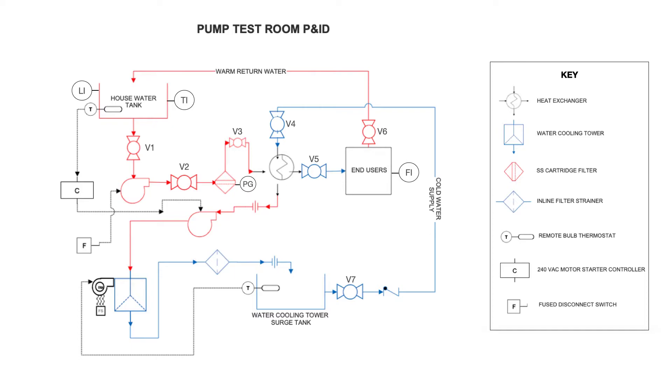You'll see that there is a remote bulb thermostat in the water cooling tower surge tank and in the house water tank. We can also see that there is a 240 volt motor starter controller that controls the water pump that pumps water out to the water cooling tower. You see there's a fuse disconnect switch that controls the pump that pumps the water out to the end users in the pump test room.